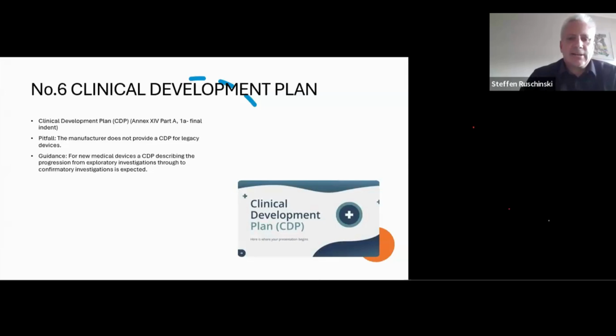The manufacturer does not provide a clinical development plan for legacy devices. People always think that this plan only has to be submitted or included if we have new submissions, but this is not correct. However, considering the regulatory status of legacy devices, this level of detail is not expected, and rather the CDP may focus on the strategy to obtain clinical evidence in line with MDR Article 61 requirements and, of course, the planned PMCF activities. If applicable, the CDP should also always include a justification for any deficiencies in relation to previously conducted first-in-man studies, feasibility or pilot studies, confirmatory investigations, noting any reference to PMCF activities that are ongoing or reference to the PMCF plan described in Annex 14.